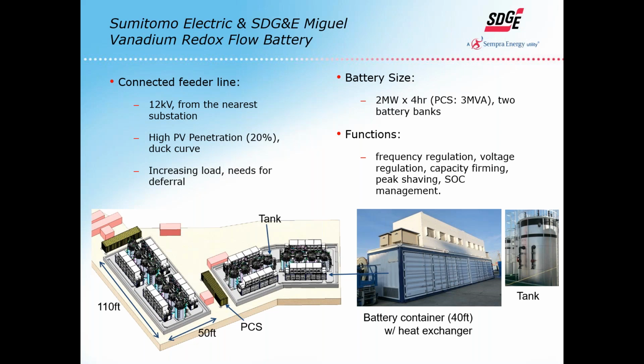This system is connected at the 12 kV level. It's actually at the end of one of our circuits, so it's a unique position, but this particular circuit has high PV penetration, as well as an increasing load toward the end of the circuit. This allows us to maybe defer other projects, because this battery can come in and provide additional functions to support that load.